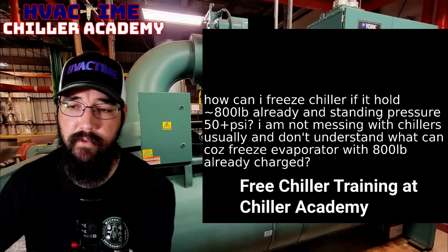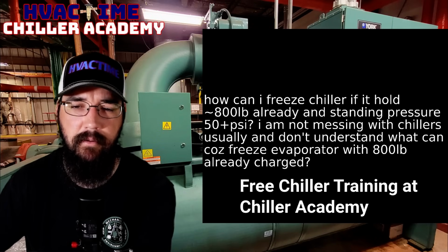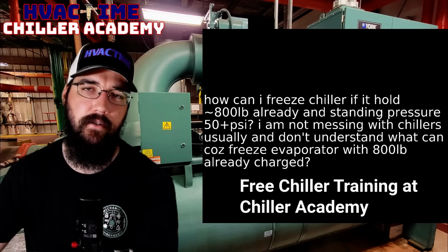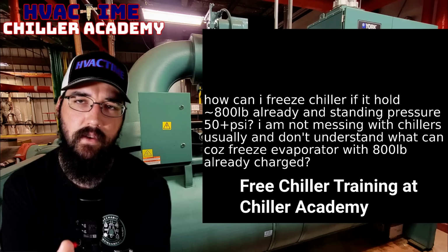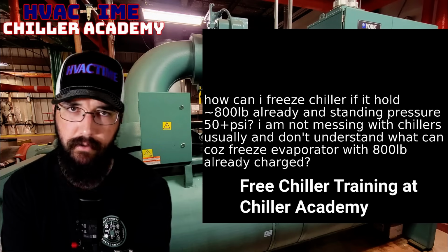We don't know the refrigerant type you're dealing with, but being that you've got 800 pounds and you're at over 50 psi, I'm going to assume it's probably 134 maybe. Either way, the key here is your saturation temperature. We need the saturation temperature to be above freezing, period.